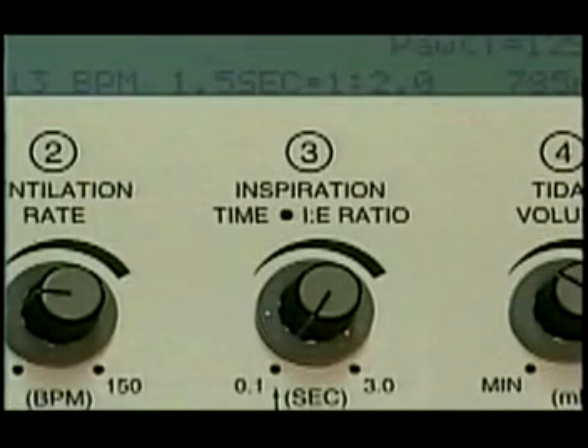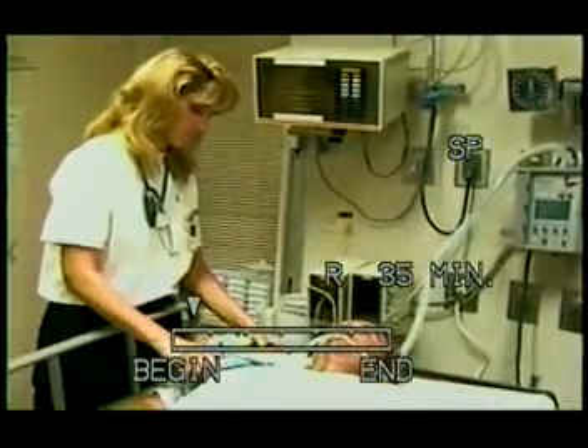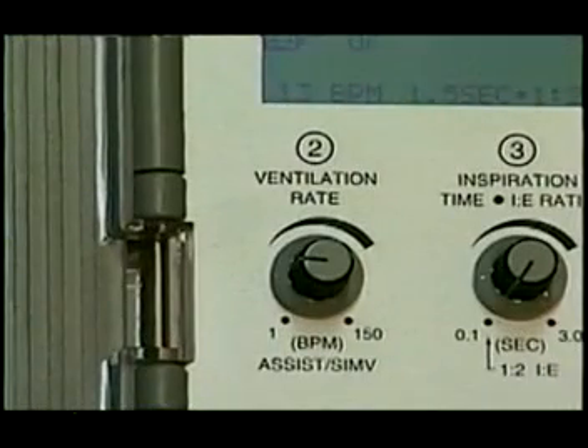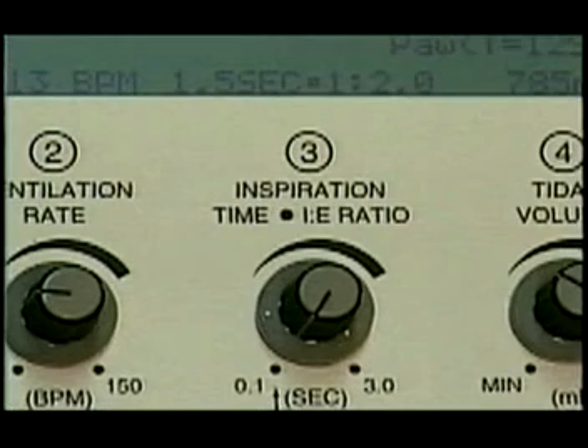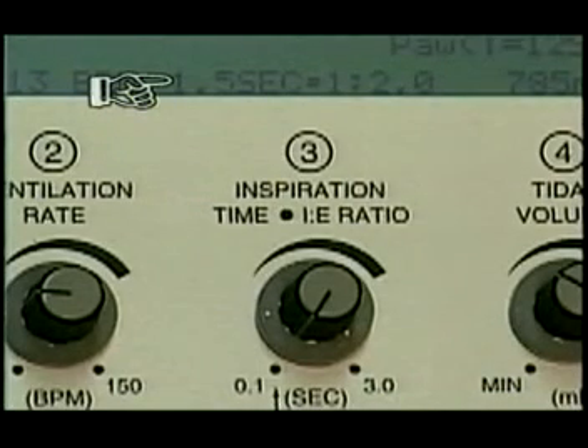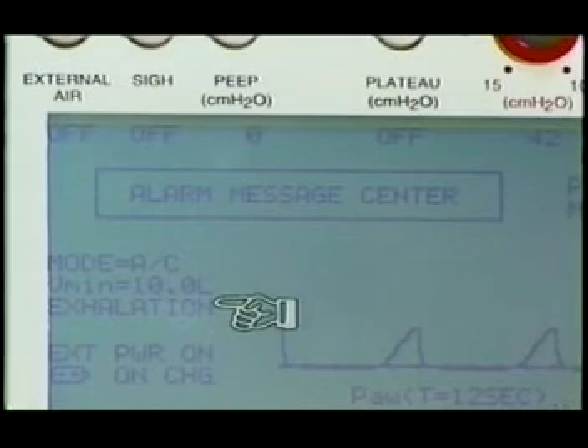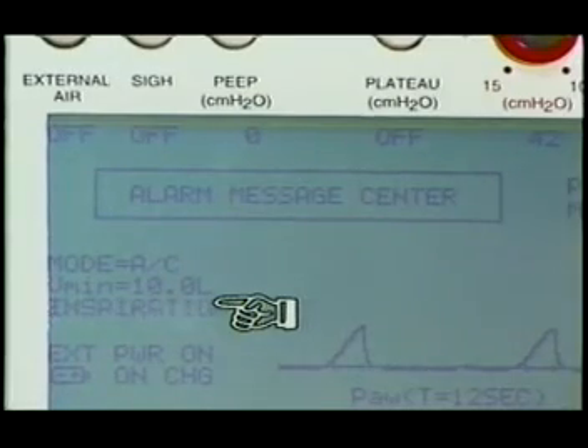The inspiration time, I:E ratio control, is the control numbered 3. It sets the inspiratory duration for all ventilator-assisted breaths. Its usable range is limited by the ventilation rate control setting, and inverse IE settings are not permitted. Depending on the ventilation rate control setting, inspiration time range is 0.1 to 3.0 seconds maximum, which is based on the current control position. Both inspiration time and IE ratio are displayed in the LCD above this control. A fixed 1 to 2 IE ratio is provided at the fully counterclockwise position. The inspiration-exhalation indicator alternately displays the inspiration and exhalation phase of mechanical and/or spontaneous breaths.